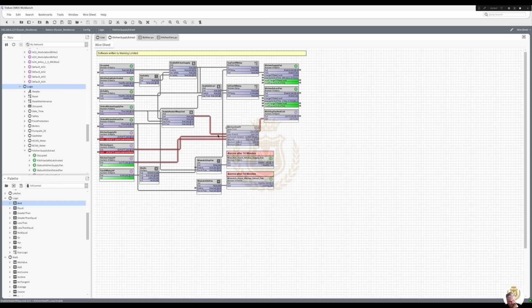So we enable the PI loop for the heater, and our control variable is going to be the kitchen space temperature, and the set point is the space temperature set point. And if it's too cold, then we heat up. And that's basically it.